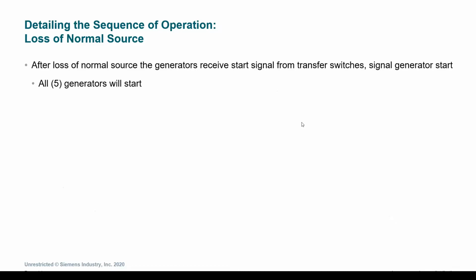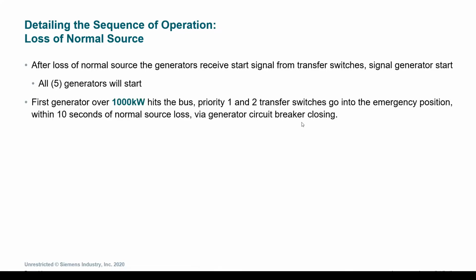After the loss of the normal source, the generators receive that signal from the transfer switches, signaling the generators to start. At the beginning, all 5 generators are programmed to be started. From here, we want to make sure that the first generator online can carry the full load of the priority 1 and 2 transfer switches going into the emergency position. As such, the first generator over 1000 kW that hits the bus will carry that load.